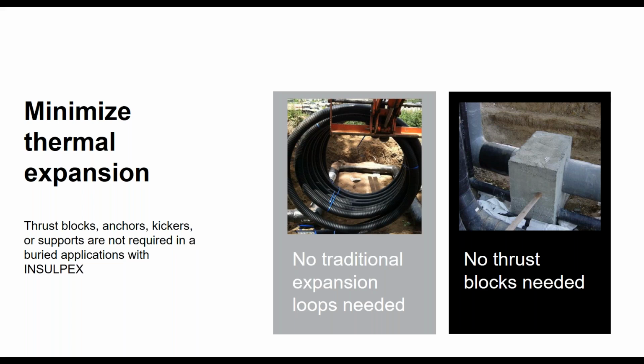Another accessory needed with rigid systems is called thrust blocking, shown in the picture on the right. You have to pour a concrete block around fittings in both hot and chilled water systems to prevent fitting pullout. As the pipe expands and contracts, it eventually puts enough stress on a PVC, copper, or steel fitting that it could fail. So you pour concrete around the fitting to encase it so that doesn't happen. The cold expansion fitting sleeve technology that REHAU endorses prevents this fitting pullout from happening.